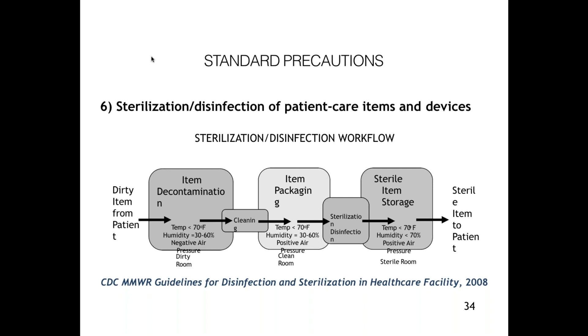packaging is event related, not time related. So as long as you don't have contamination, in theory, your sterilized packs can last forever. It's event related, not time related, unless they're contaminated. But your storage has to be in controlled humidity areas. It has to be less than 70%. That's the big one, right? Because if they get wet, then you can't vouch for things. You have to re-sterilize.